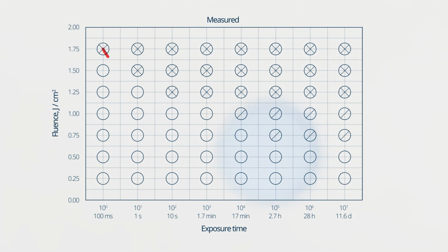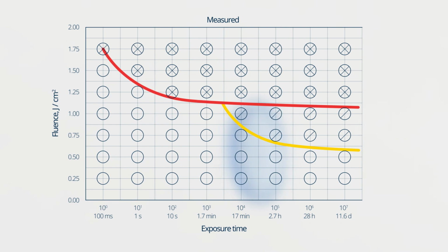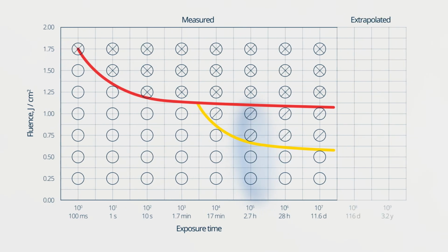Collected statuses and damage statistics are then used to calculate the damage threshold of every failure mode for the applied laser pulses, or exposure dose S. By having LIDT data trend versus the time, it is possible to use extrapolation to make a prediction of the future. By applying advanced statistical methods, a prognosis of long-term behavior is made for each failure mode.